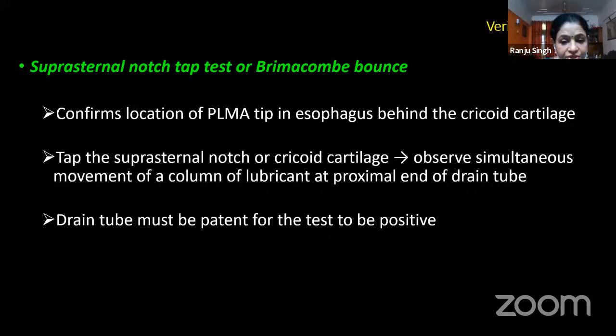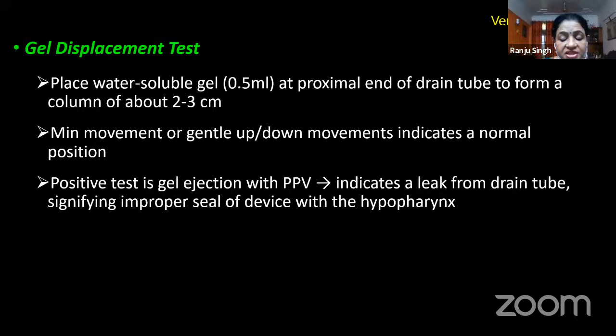Another test we can do is called the gel displacement test. Again, you can place some amount, like 0.5 ml to 1 ml, of the water-soluble gel at the proximal end of the drain tube to form a column of about 2 to 3 centimeters. A minimum movement or a gentle up and down movement of this column of gel while ventilating the patient indicates a normal position. A positive test is when the gel is ejected out with force with positive pressure ventilation.